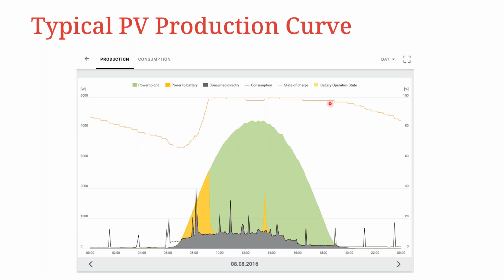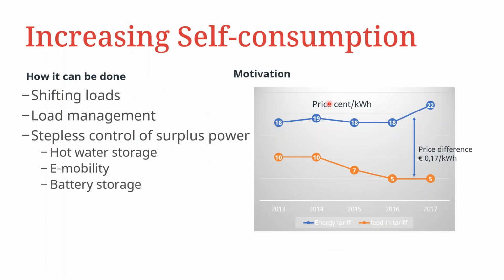So how can you increase self-consumption? This can be done in three ways: shifting loads. So if some loads are probably operating outside of PV production, you can decide to shift when these loads are operating. You can also do load management that we have just looked at to ensure that some specific loads are only active when you have surplus energy available in the network. And then you can also do stepless control of the surplus power, which can be directed for hot water generation, can be done for EV charging as well as battery storage.